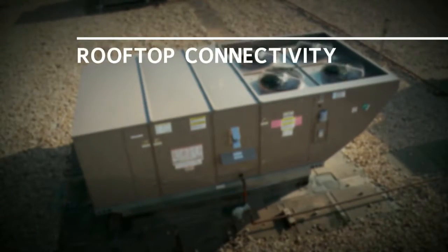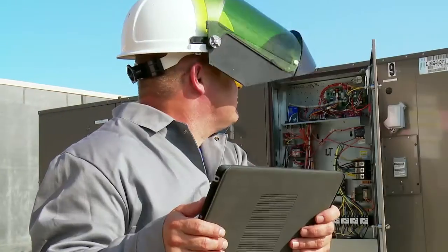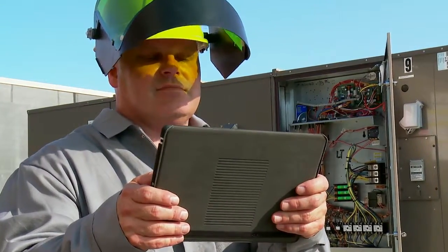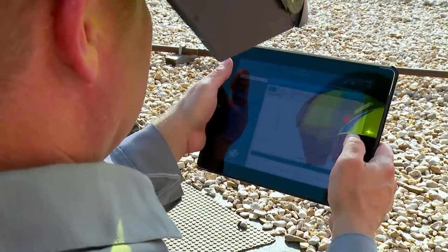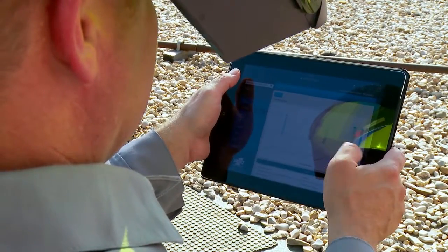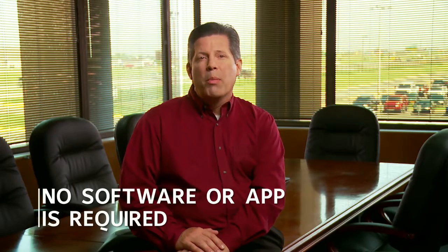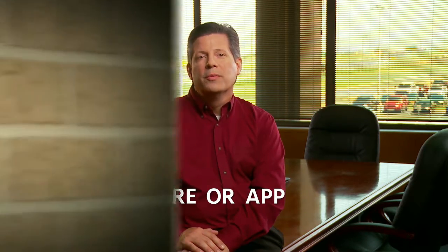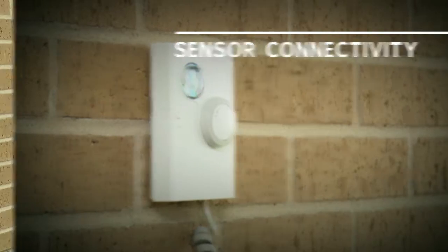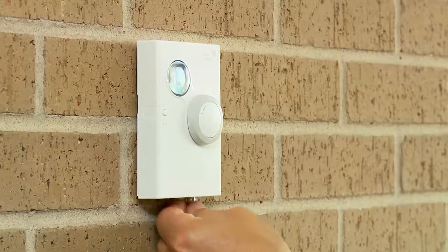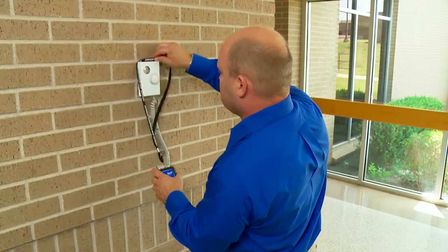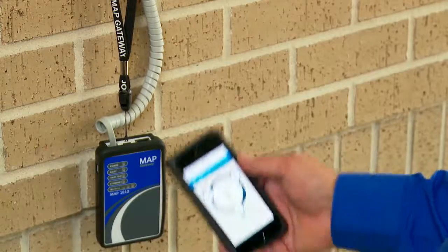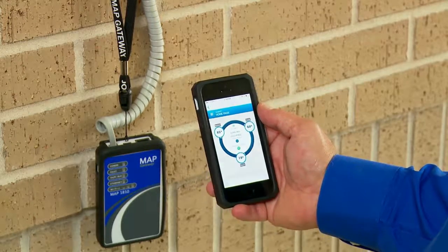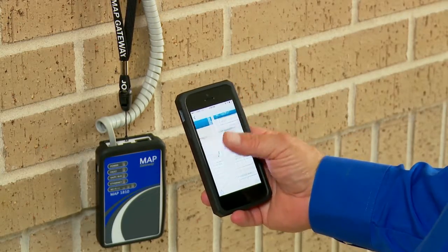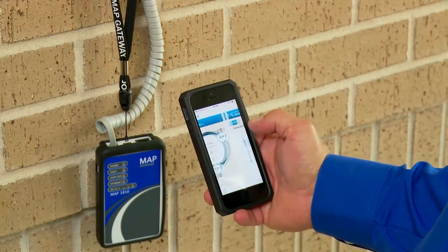At the rooftop level, you get the option of connecting with a smartphone or tablet using the Mobile Access Portal, or MAP Gateway. Then you can use the web browser to access operational data, set points, schedules, and diagnostic data. No expensive software or bothersome app download is required. Now let's look at the connectivity at the sensor level. The MAP device easily connects with the wall sensor. Essentially, the MAP device becomes a Wi-Fi access point and a web server that displays control screens in a web browser right on your mobile device. It's a gateway direct to the unit to give you total access to all the operating parameters and data logs.